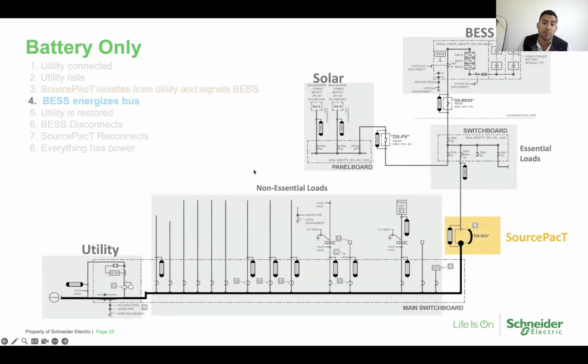They're smart inverters. So once we're disconnected from the primary service, that motorized breaker and SourcePacT will open up. We'll send a signal to the inverter system, the energy storage system, to become the emergency anchor resource. Now it's providing backup power to that essential switchboard. At the same time, your PV system will recognize that we have an available anchor resource to parallel to and will come online. Now you're providing power to those essential loads in your switchboard during a utility outage. I think we did this all by solely adding an automatic interconnection switch. You didn't have to add a specific and advanced microgrid controller to control all the utility main service disconnect. You did this being off the main switchboard and solely by segmenting those essential loads.